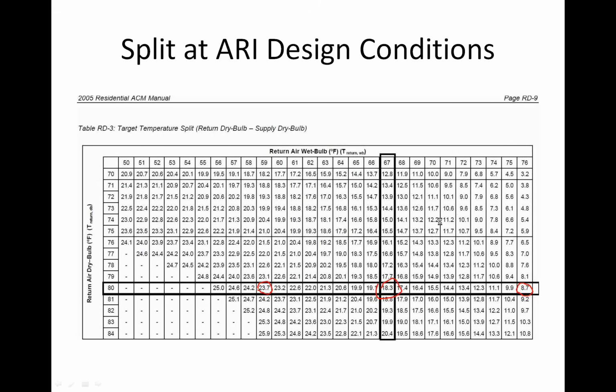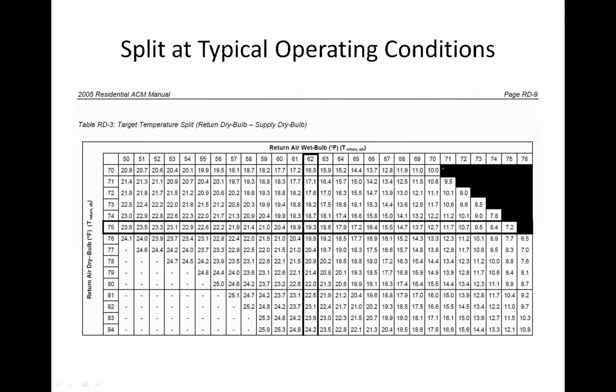One thing here, I did block out this section of the chart for those of you that are science geeks like I am. You can see here at a 70-degree return air dry bulb, the highest the return air wet bulb could be is 70. You can't be at 71, because at 70-degree wet bulb and 70-degree dry bulb, we're at 100% relative humidity. Okay, and I've blocked this section out. Somebody threw this in an Excel spreadsheet somewhere and extrapolated it out, but in reality, these sections that are blacked out are impossible. The wet bulb can never be higher than the dry bulb temperature.